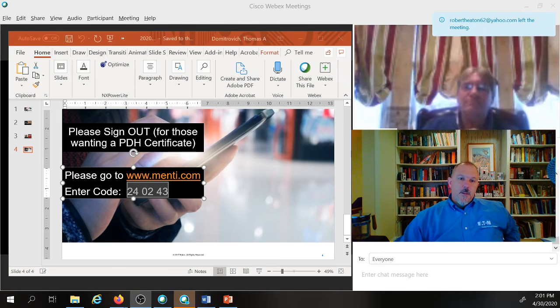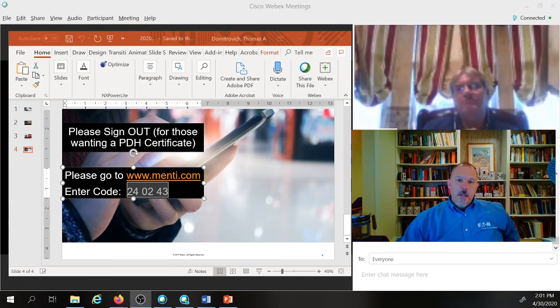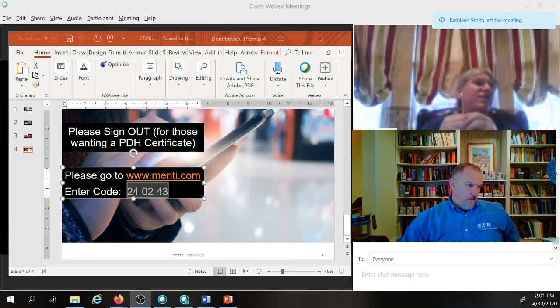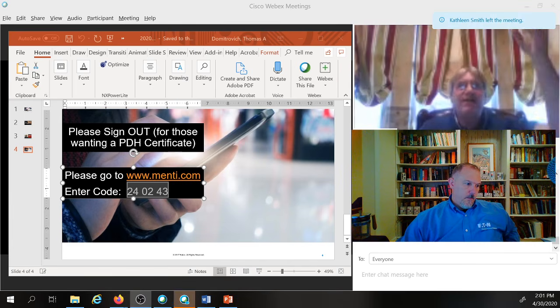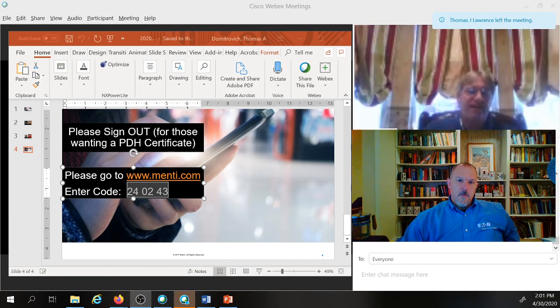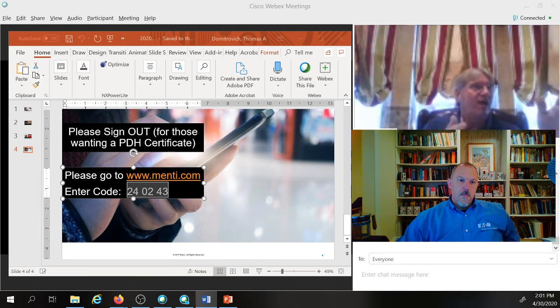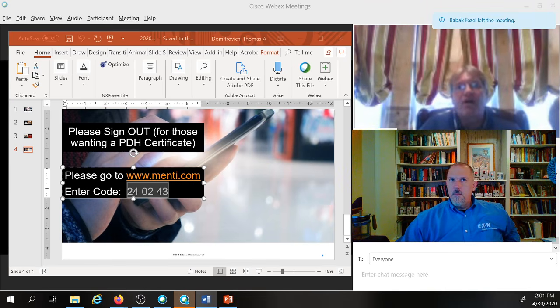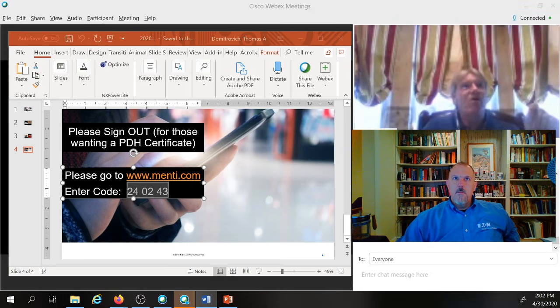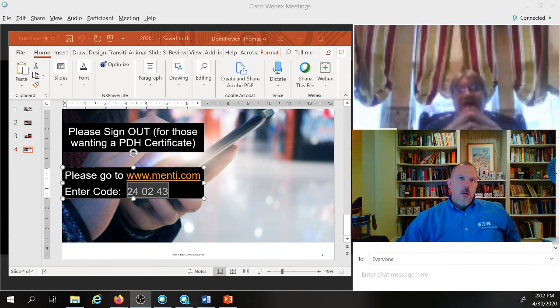Okay, so here's another good one. Why is the 12-inch pendant rule applicable for hazardous locations? This is coming from YouTube. Sure, and the concern is that if you have a pendant hanging down, let's just say 3 feet, and somebody comes by with a piece of equipment and hits the fixture, now it's going to start to move. And if they're not paying attention, it moves real far. You run the risk of the conduit sparking or the conduit actually cutting a conductor, which could create an arc, and that could ignite my gases or ignite my combustible dust in suspension. So that's why we have to make sure that we protect against that lateral displacement.